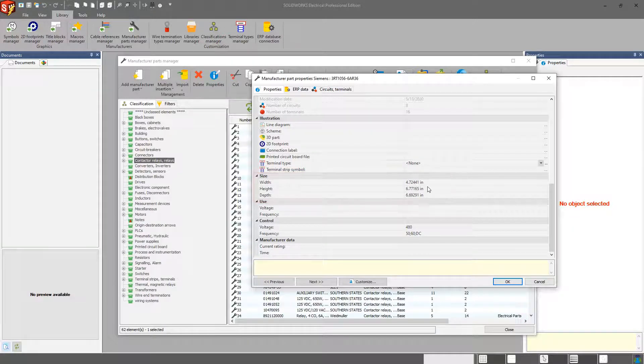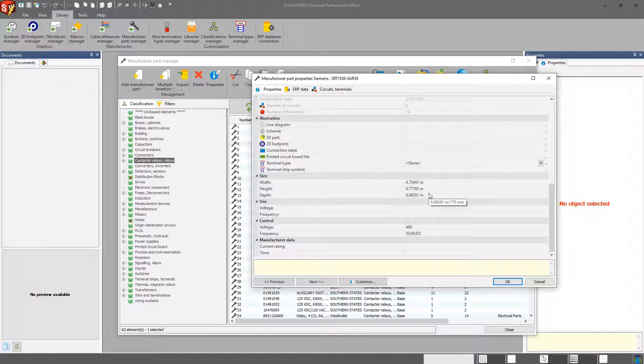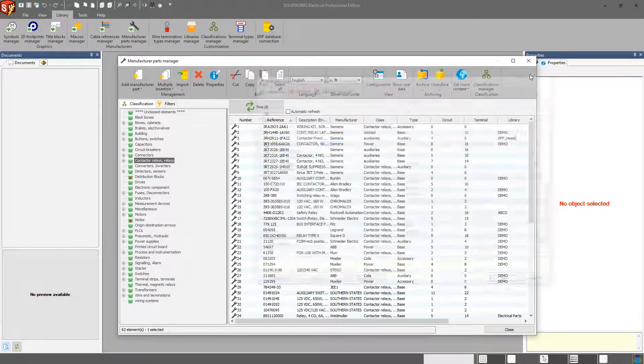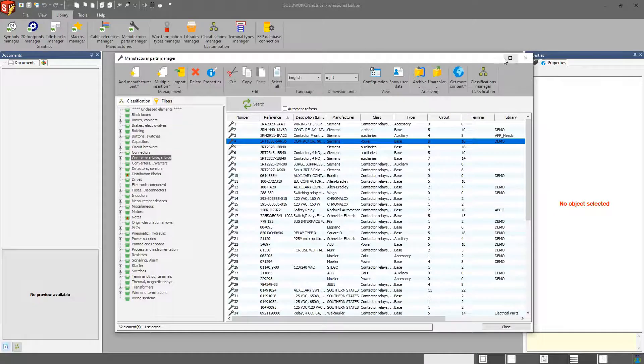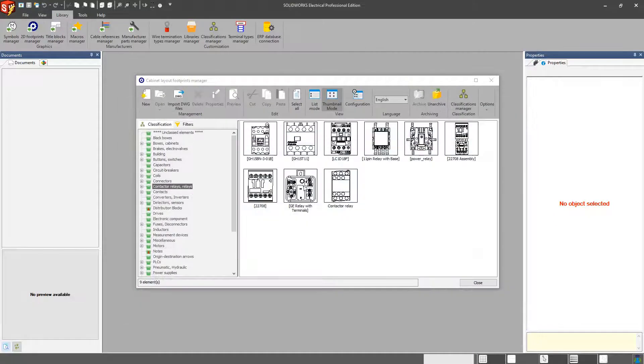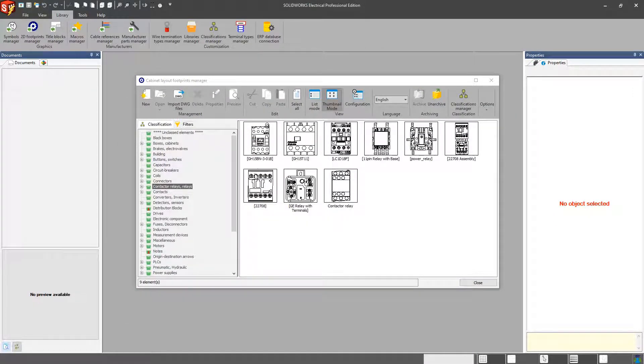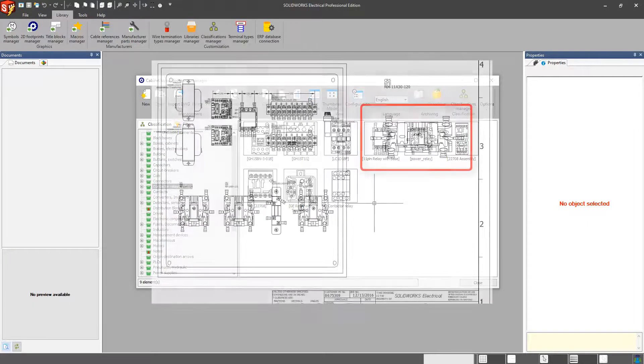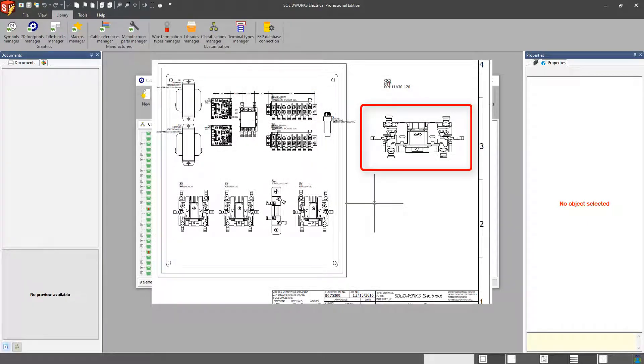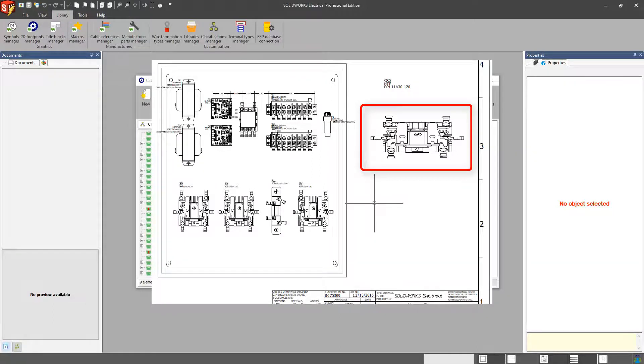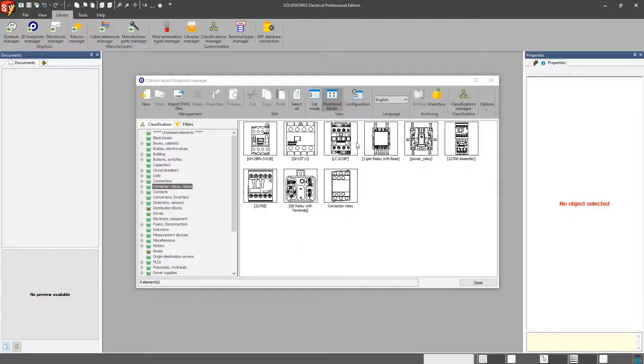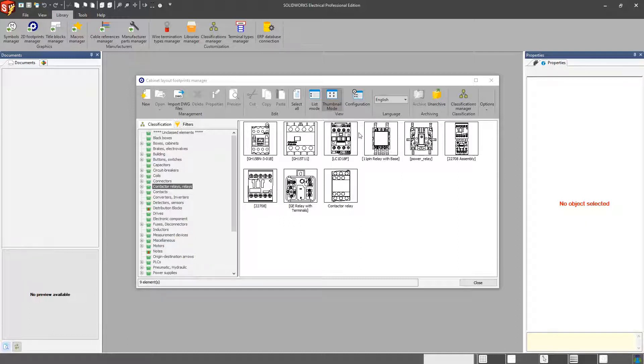Now, the dimensioning here directly correlates to what that symbol is going to look like inside of our cabinet layout drawing. So if my dimension is off in my manufacturer part for this part here, and the width is set to where the length needs to be, that symbol is going to stretch out really wide and also look very small as far as the height goes. Just be careful when you enter your height, width, and your depth. Not that you really need depth to worry about in a 2D tool, but maybe you generate a report that you need to know that information.